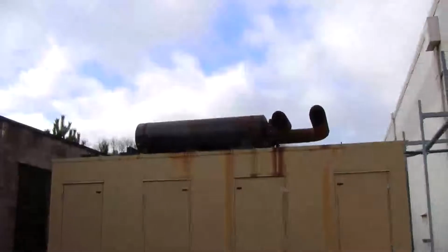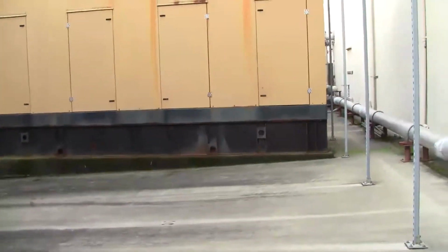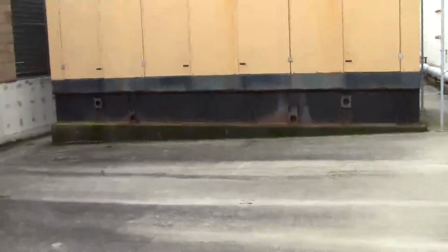And have you mentioned what powers the generator? Diesel fuel. Diesel fuel, okay. Inside of this enclosure is a 1,500 gallon day tank, and then below it is a 3,500 gallon expandable tank, basically. We have this filled every quarter, and we have an agreement with 2 fuel providers already set in place where if we start running out of fuel, they will be out within 24 hours. So basically, with the 3,500 gallons and the 1,500 gallon tank, we can run for around 4 days on that, and then by then the fuel provider had better be out.